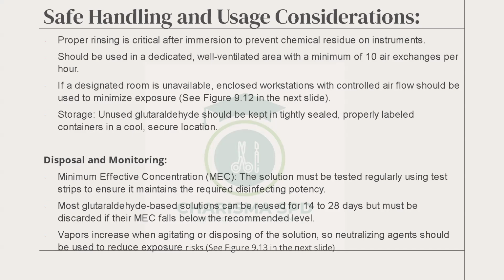In some hospitals, there is a specific room called the HLD room, high-level disinfection room. That is somehow close to the decontamination room, but it is not part of the decontamination room. It is separated, controlled. It's a cleaner environment than the decontamination room. So, the air exchange, why? Because of the odor and those kinds of things, the chemicals. We don't want people with asthma to be breathing it. Not even people with asthma, but just smelling chemicals. We don't want that. So a designated room, and hospitals are doing that these days.